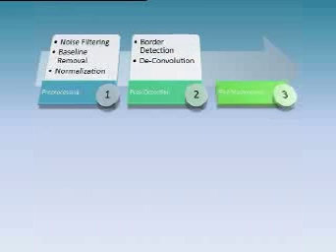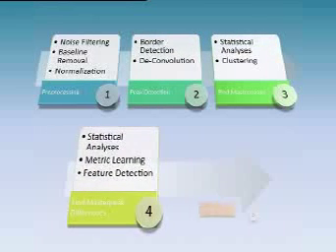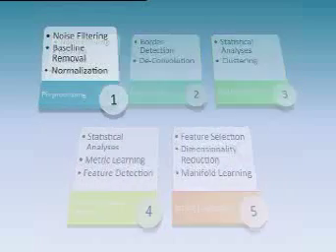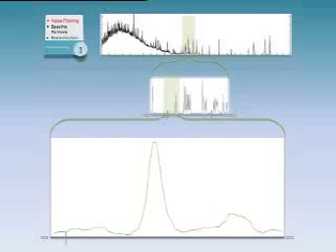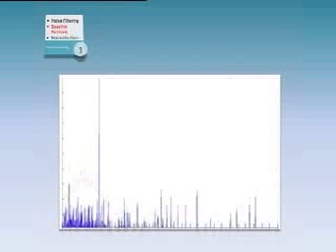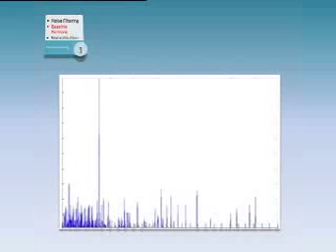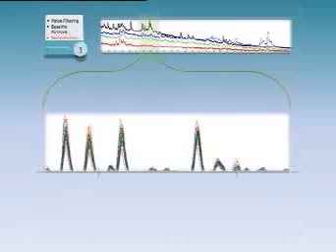Which analysis methods are needed? How can one speed up the investigation? An analysis pipeline with a sequence of new algorithms is key to a successful investigation. The process starts with the raw data coming from the mass spectrometer. Initially, this data is denoised to facilitate subsequent steps of the analysis. Following this, the so-called baseline is detected and removed. Afterwards, the spectrum is normalized to establish a common level so it can be compared to other spectra.